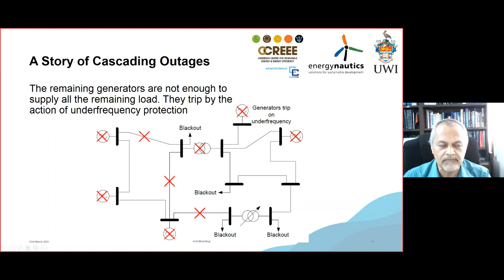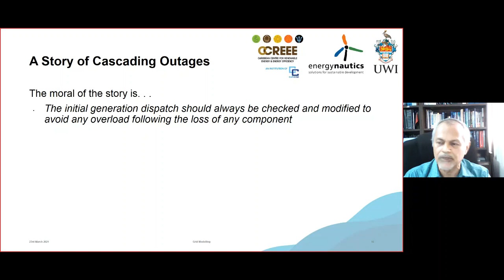The moral of the story: the initial generation dispatch should always be checked and modified to avoid any overload following the loss of any component, and I also have to check my protection system. One error many people make in power system analysis is forgetting that once the system changes, if I add a line, remove a line, or a line goes into maintenance, my protection system also should be checked to make sure I do not compromise the security I had. We need to do this almost on a regular basis to ensure my system is properly coordinated and protected.